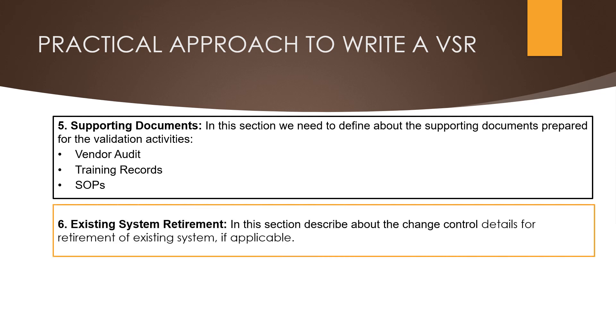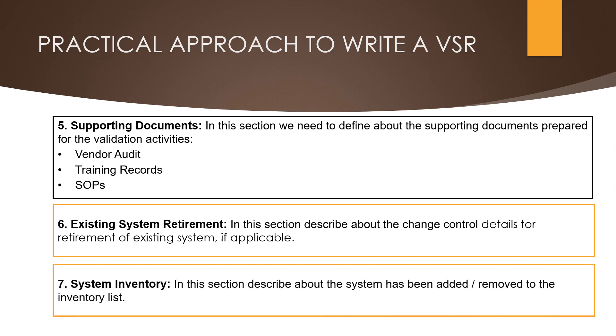The sixth component of the validation summary report is existing system retirement. In this section, if not applicable, we need to describe it as not applicable. The seventh component is system inventory. In this section we need to describe whether the system has been added or removed from the inventory list. As per GMP practice, an inventory list should be maintained for all systems available in the department, and this list needs to be updated once the system has been validated.